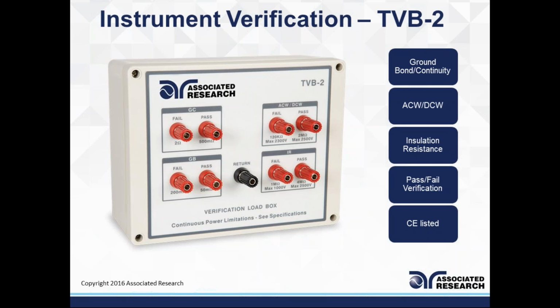Just for a quick example, the way this box works is, if you're trying to verify a hipot tester, an AC or DC withstand tester, there are going to be two tests, a fail and a pass verification. You take your high voltage lead and connect it to the fail side, and the return to the return on this TVB box, and set up the parameters accordingly. The spec sheet specifies all the appropriate parameters that are allowed to be used, and a simple pass-fail verification can be achieved by performing the actual tests.